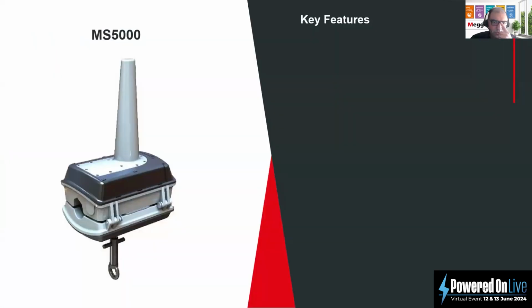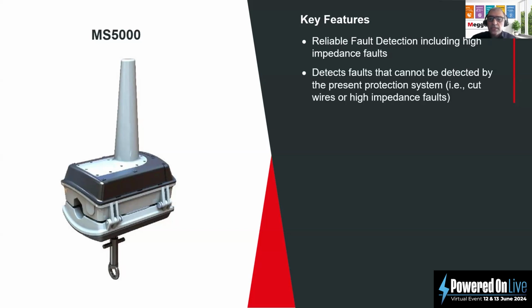We introduced the smart sensors called MS5000 for overhead lines. Some of the key features of the smart sensors are reliable fault detection, including high impedance faults, which we will talk about more later. They detect faults which cannot be detected by the primary protection system, or which the protection system in the primary substation is not designed to detect, like high impedance faults or cut wires.